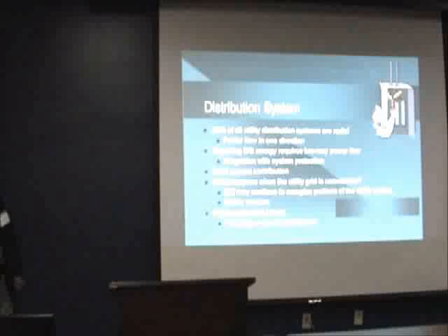And then, what happens when the utility grid goes down? What's DG again? I'm sorry. Distributed generation. Yeah, DR, distributed resource, DG, distributed generation. I kind of switched on you, sorry. But what happens if the utility grid is unavailable, or portions of it? The DG might be just fine, right? And keeping that distribution line energized. So the guy from the utility goes out there to work on a power line, he expects it to be dead, but doesn't realize that we got a generator out there that's keeping the system live, right? So it has a safety concern to it.